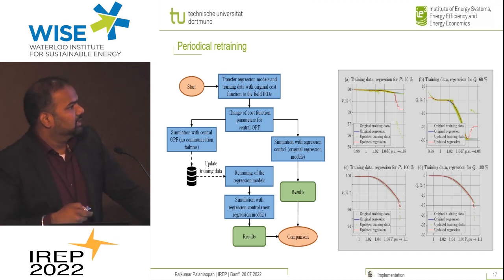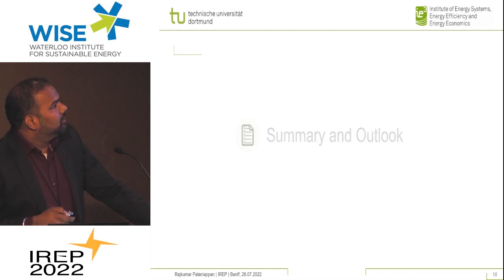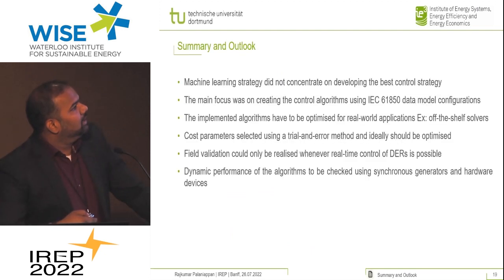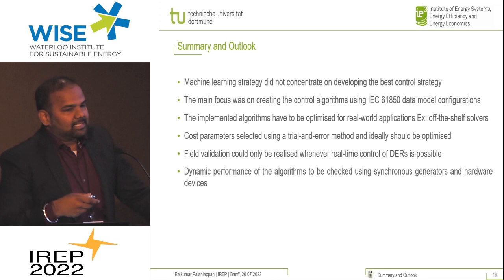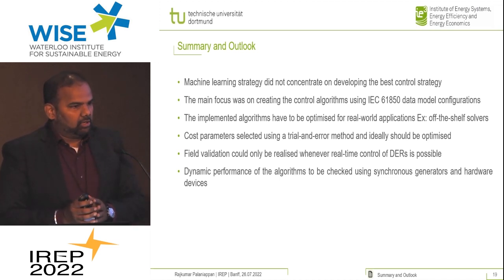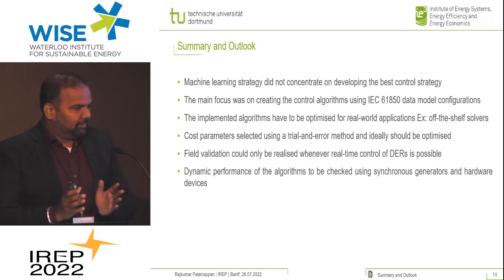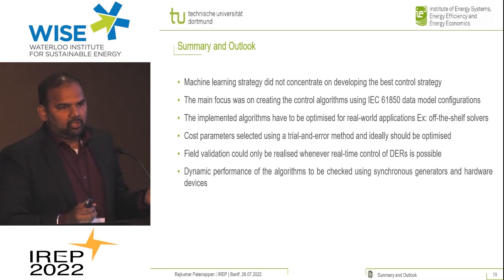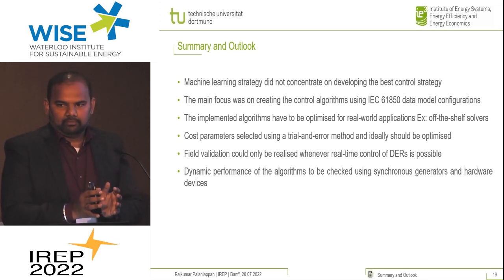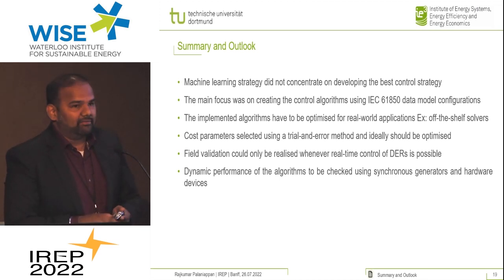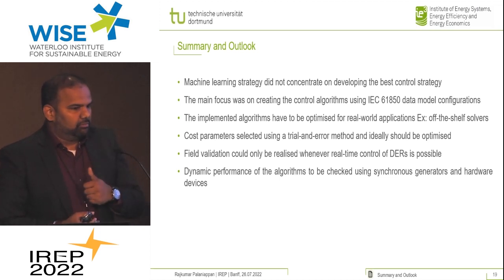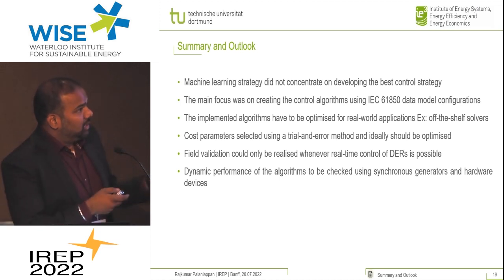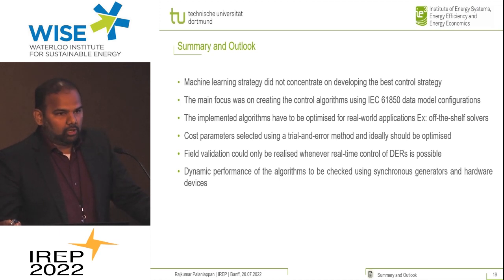So that's the idea of this implementation. Coming to the summary and outlook - as I said earlier, the control algorithms or regression algorithms are not the best case strategies. The idea is separation of hardware and software, usage of 61850 data models, and having one device that can do everything. Because this device, at least what we have, is a power quality measurement device, it can do protection algorithms, control algorithms, and exemplarily we tested with machine learning algorithms too. As we see here, it is possible. If we want to extend the algorithms, of course we can do it.